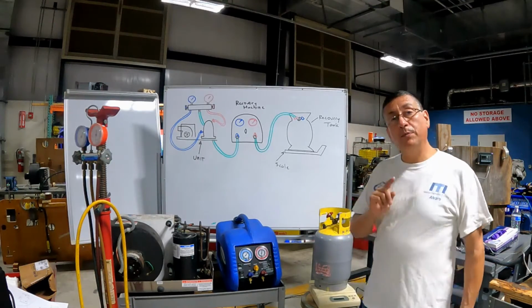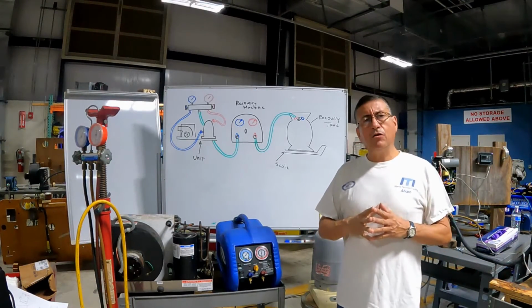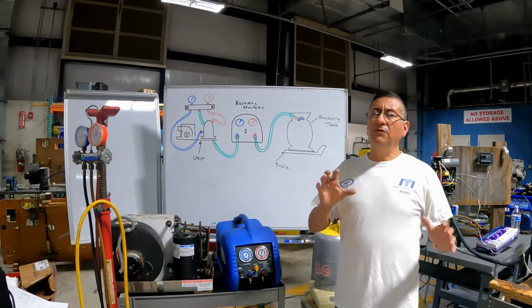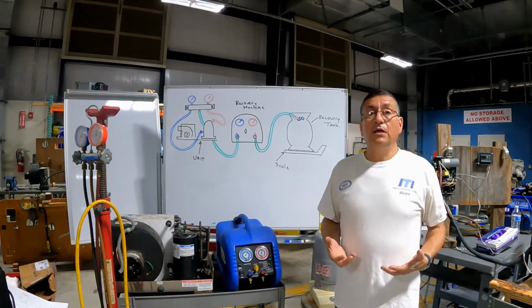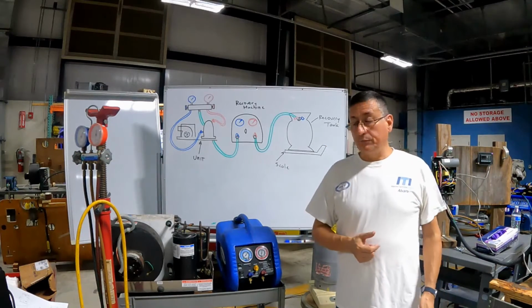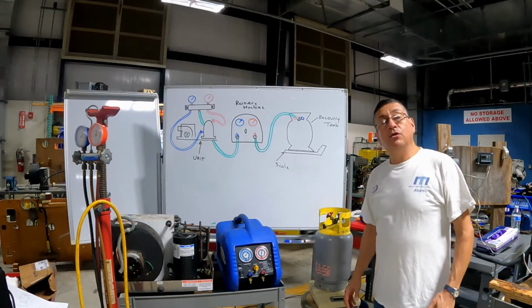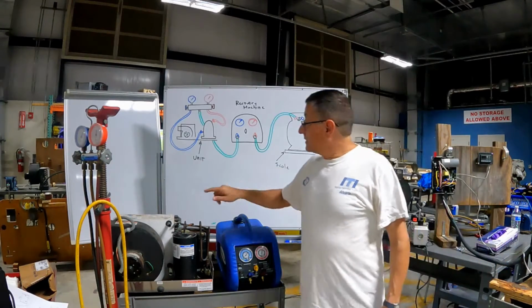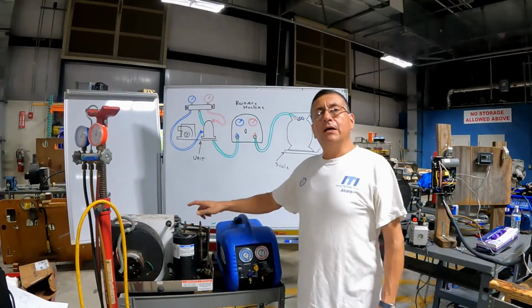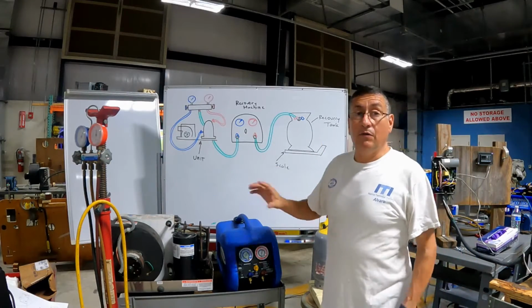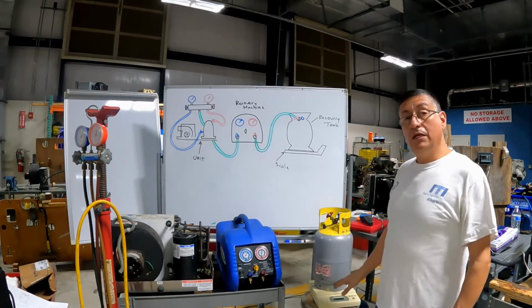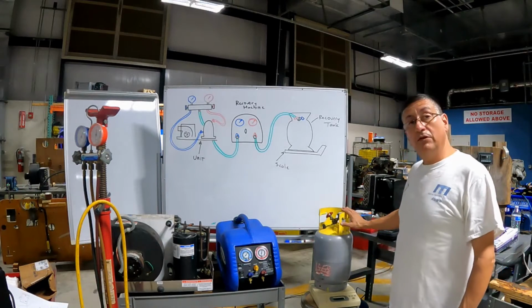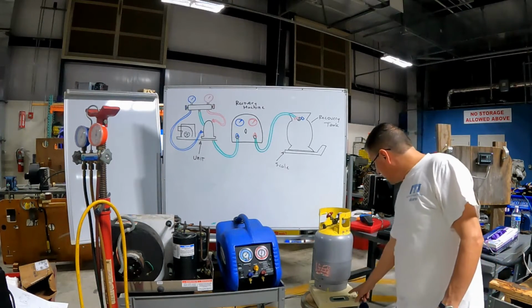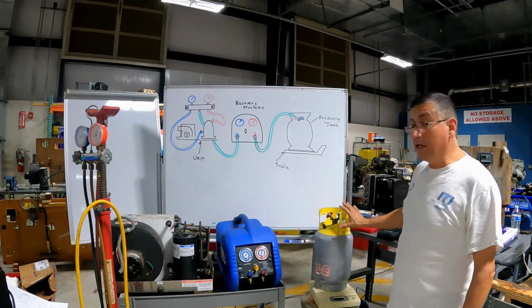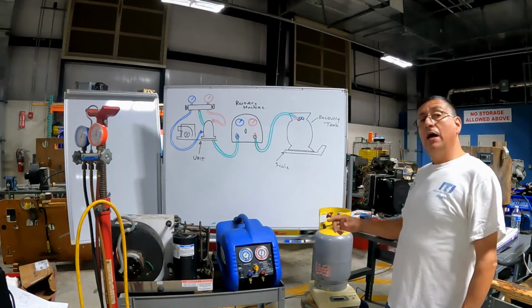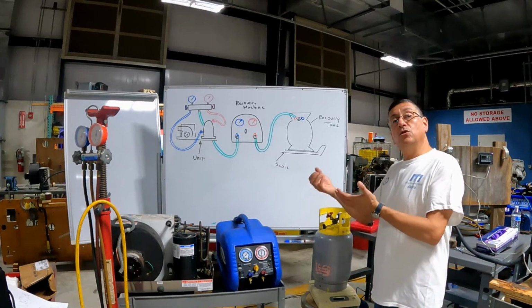And select the cylinder appropriate for the refrigerant. For that reason, I recommend that in your car, in your minivan, you try to keep different recovery tanks depending on the refrigerant commonly used in your boats. Okay, additionally you need a scale, because the idea is to recover the same amount of refrigerant and put back the same amount. In order to avoid mistakes, it's a good idea to verify the weight of the cylinder. You need to weigh the empty cylinder and verify how much refrigerant you can recover.